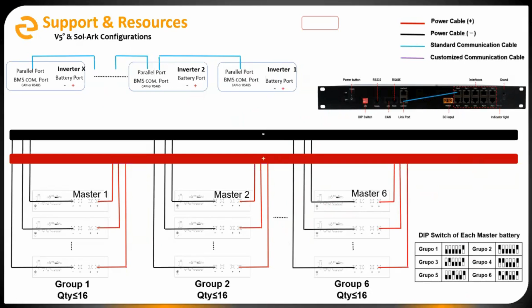I'll keep it moving, but again, just showing how we do these larger systems where we have multiple groups of batteries. We use our hub - common bus for all the batteries, common bus for all the inverters, they all share that. These are all standard Ethernet cables between the batteries, from each battery group to the hub, between the inverters even. In this case, there's a special cable we need from the hub to the inverter, which we can advise on when the time comes. If anybody's doing an installation of this scale, don't hesitate to reach out to us - we can offer some input, make sure everything's set up correctly and functioning well. So we set the dip switch on the master battery of each group, and then set the dip switch on the hub to match with the inverter.